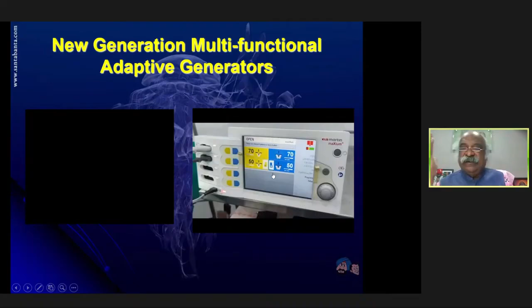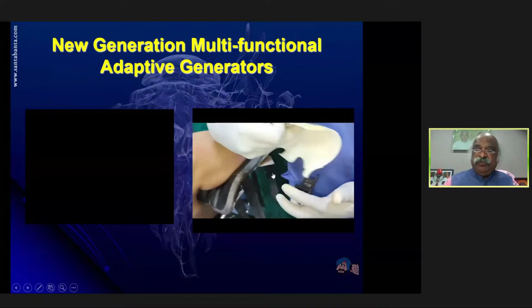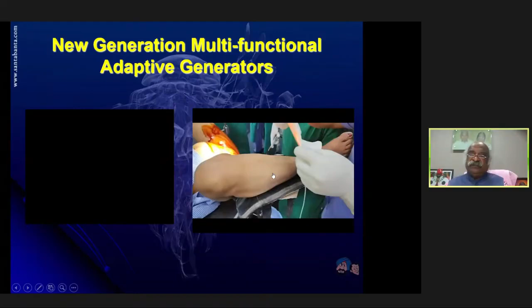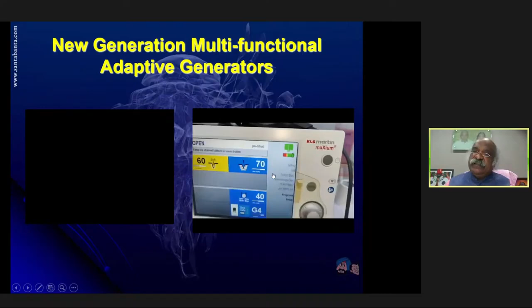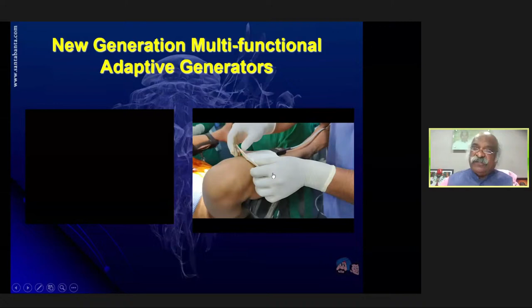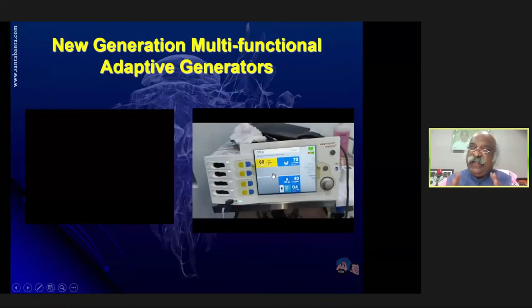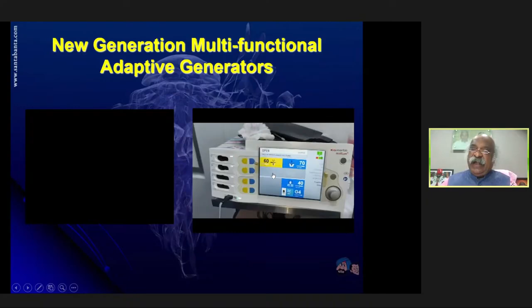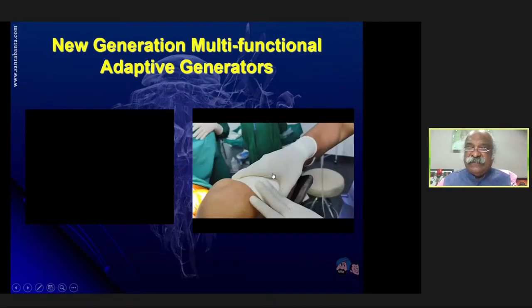This is the pedal patient foot plate, which can also be remote. There's a remote foot plate on one side, and the patient plate on the other. The right application of the patient plate in the right place is very important. The main surgical philosophy is to place it over a muscular area, not over bony, irregular, or scarred areas, and closer to the surgical field. When you raise it, a red signal appears from the auto-sensing device, and when it's completely intact and normal, it shows a green signal.